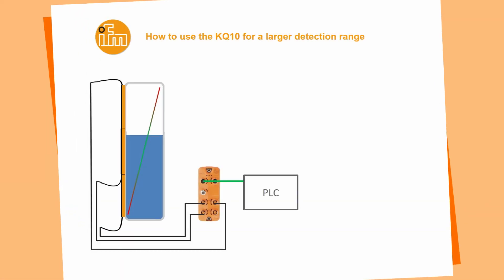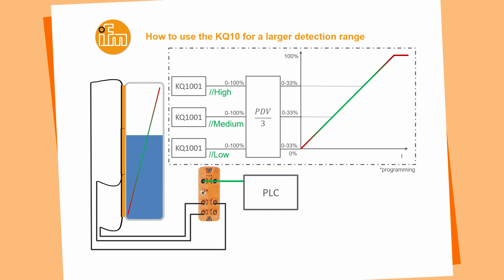When we are using the KQ10 for a larger detection range, for example for a larger tank, we just have to connect the sensor to an IO-Link master and go from the IO-Link master to a PLC. Inside of the PLC, we are collecting all three process values of the KQ10. In this case, I called them high, medium and low. We take the process data value, divide it by three and we get a process value from zero to 100%.